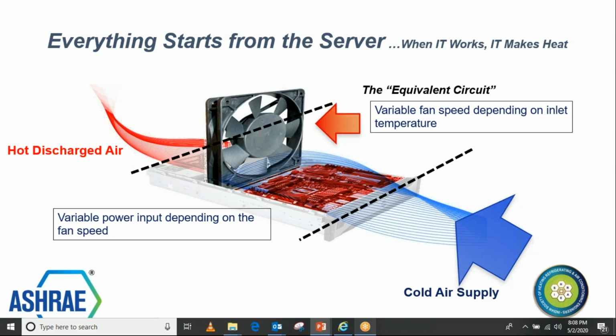CFM required and just throw it in the room. It is important to consider what temperature you have to maintain in front of the application equipment, and for this temperature which you want to maintain, what air quantity you need to deliver there, and how efficiently you are able to deliver this air quantity in front of the server, a switch, a VFD panel, or any other equipment. That will define the overall distribution and overall efficiency of your cooling system.